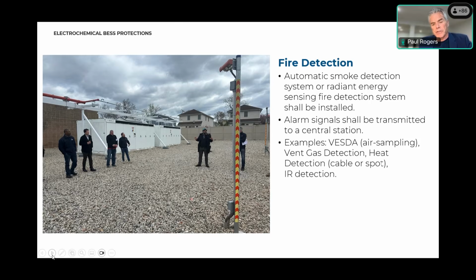I thought that was a great add-on, and then that they actually do that. And there's other examples of it, which is a VESDA, very early smoke detection apparatus. It's an air sampling system, and that may be for things that are outside of lithium ion. It could be lithium ion too, but basically it's an air detector, constantly sampling the gases inside the room itself, and it can set off a signal to actually get the fire department running. What we have also seen out there, and this is becoming more common, is these IR detectors. The IR detectors are really looking for flame. Most of the time they're looking for flame. In some cases it could be heat, but all of that would actually trigger an alarm to get the fire department rolling.